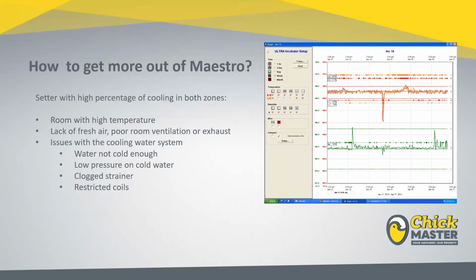Also, with machines that have filtering or a strainer on the chilled water, it's a possibility you may have a clogged strainer. And a lot of times with older multi-stage machines, we'll commonly see cooling coils that are restricted. In other words, over an extended period of time, debris or rust particulates settle into your chilled water system, and these will find themselves into the chilled water coil, and it's really hard to get that debris out of there without just opening the coils up and flushing water through. But a restricted coil will also act like a plugged strainer, and you'll see that with machines that are running excessive volumes of chilled water just to try to maintain the temperature.